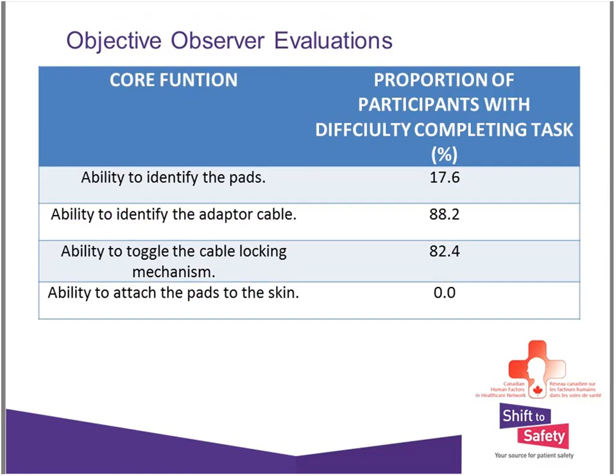Actually, maybe I'll just skip ahead here if I can get a picture of it. Go back here. I'll explain it now. The adapter cable is found on the cart and needs to be connected to where that battery is. And most people don't know where to connect that because there are actually 3 or 4 different ports that look like you can connect it to. And then once you have applied that adapter cable appropriately, you have to put it into the cable locking mechanism. And I'll show you on pictures later on, this green little locking mechanism is located at the bottom of the defibrillator underneath a handle.